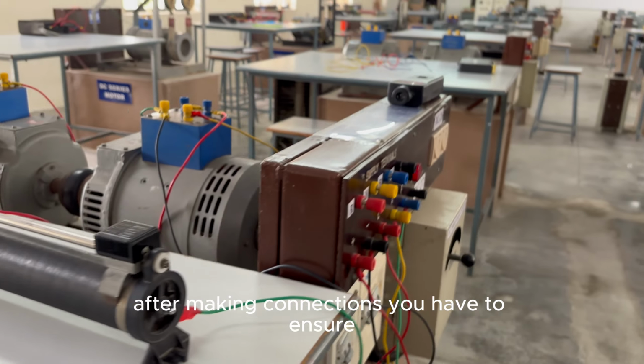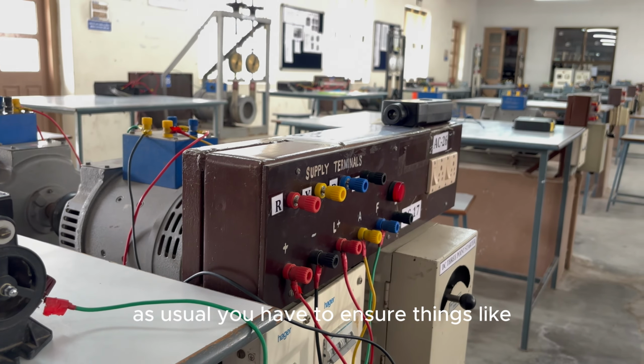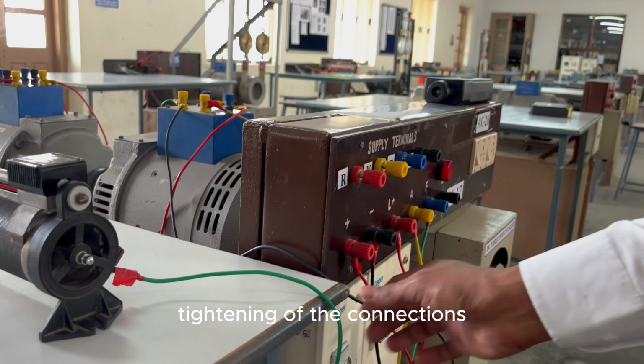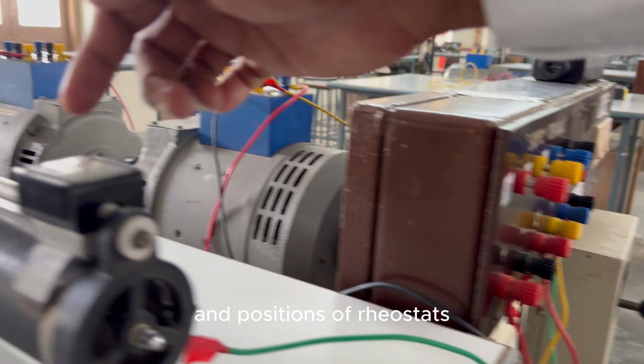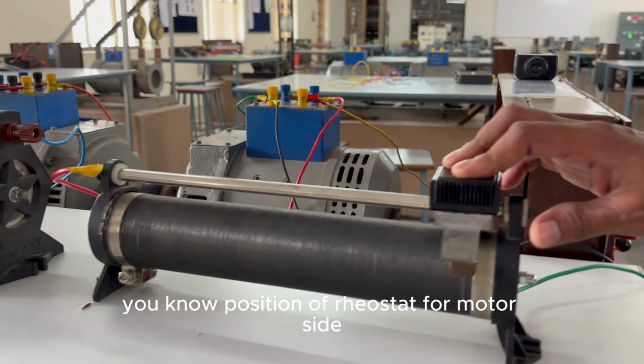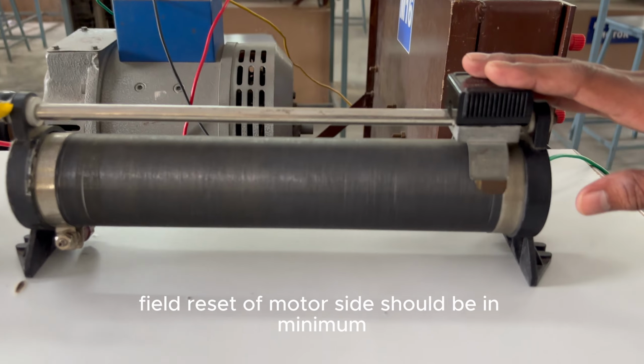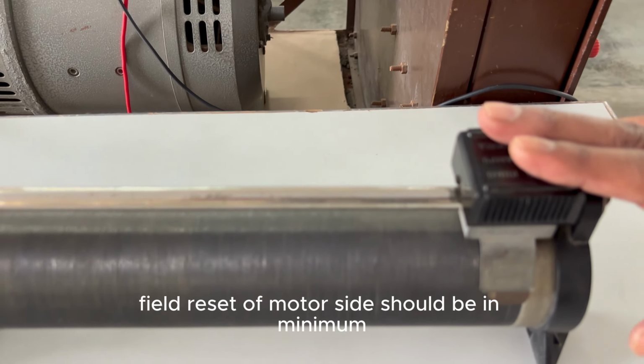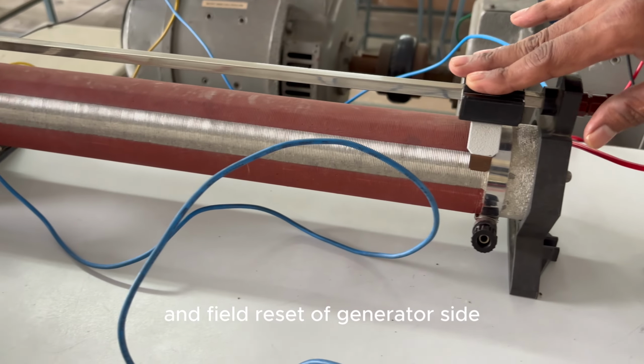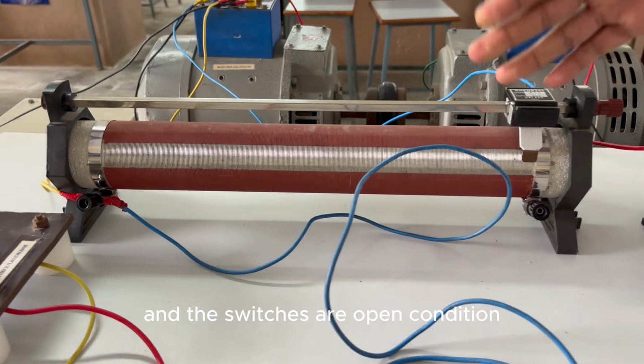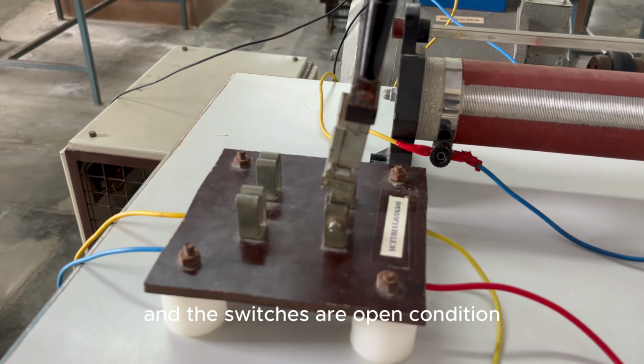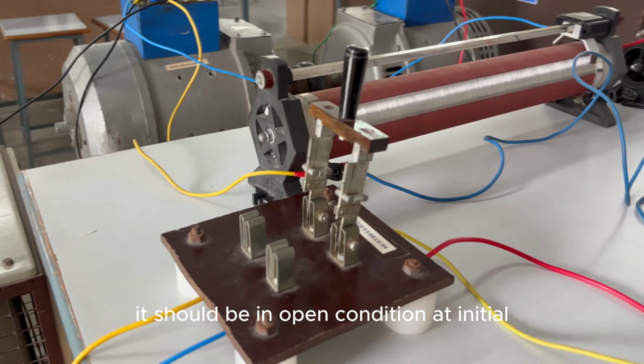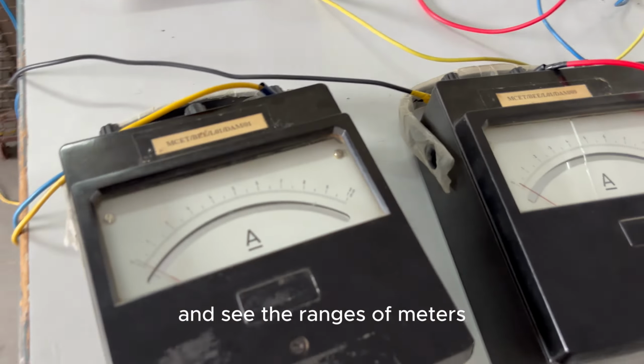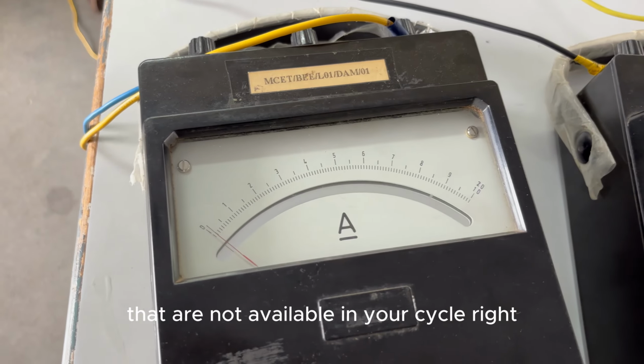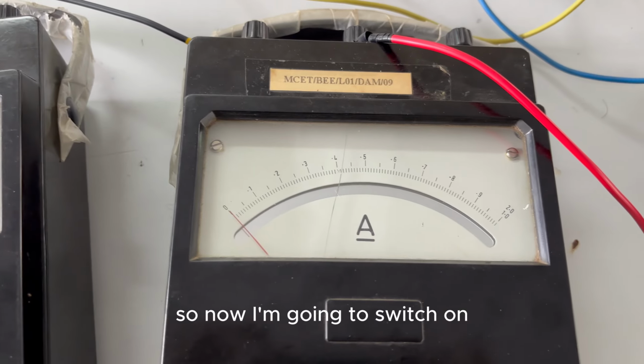After making connections, you have to ensure things like tightening of the connections and positions of rheostats. The field rheostat on the motor side should be at minimum, the field rheostat on the generator side should be at maximum position, and the switches should be in open condition initially. See the ranges of the meters, which are all available in your cycle diagram. So now I'm going to switch on.